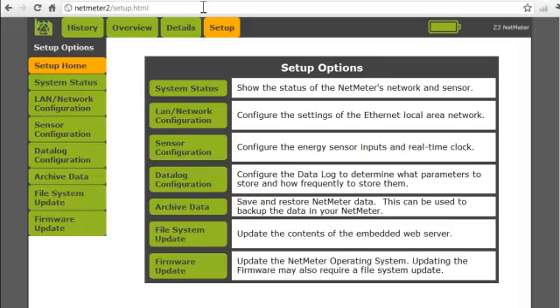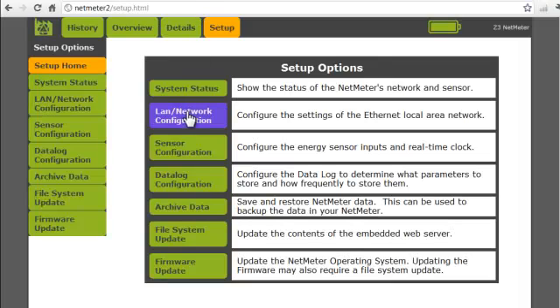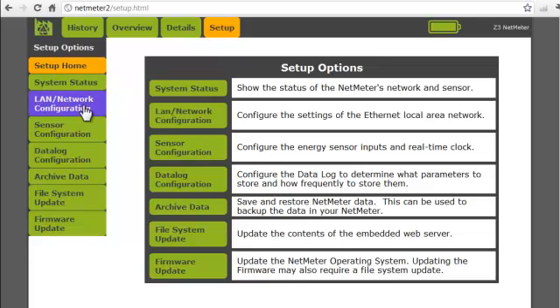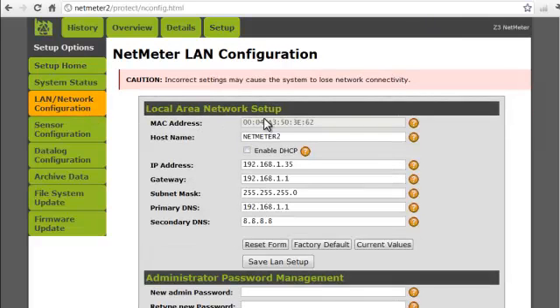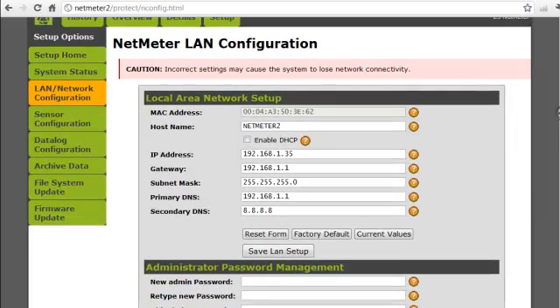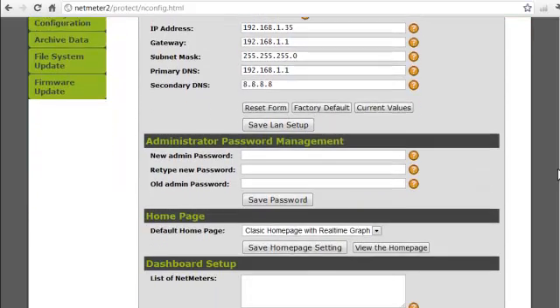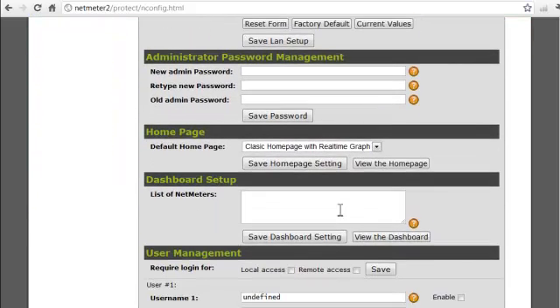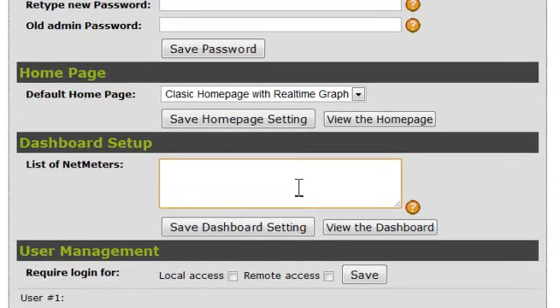Start by going to the Setup menu of the NetMeter that you are going to designate as the dashboard host. Select the LAN network configuration option. Note that you will require the administrator password in order to proceed. Go to the Dashboard Setup section. In the List of NetMeters box, you need to enter the IP addresses of the NetMeters that you want to include in your consolidated report.